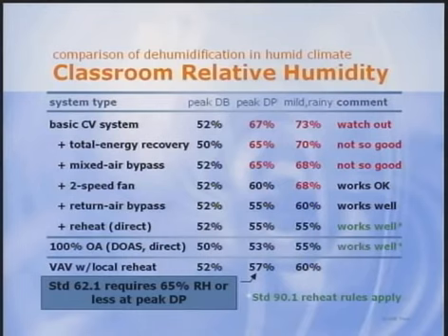100% outdoor air systems with a dedicated outdoor air unit can meet the standard 62 RH limitation, provided the dehumidified outdoor air is drier than the air in the zone. Even if the outdoor air is reheated, this approach usually meets standard 90.1 since heat is only added to ventilation air. And finally, most VAV systems deliver dry primary air at all conditions, so they maintain reasonable zone humidity without humidistatic controls. We covered analysis of these and other dehumidifying systems in detail in an earlier broadcast and in an applications manual. In summary, to comply with standard 62.1 requirements for dehumidification, pick the right system and control it right. Mick?